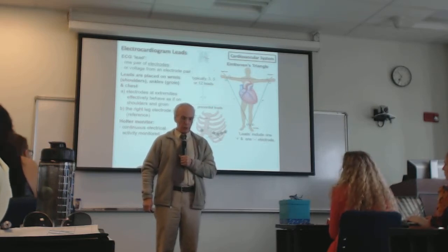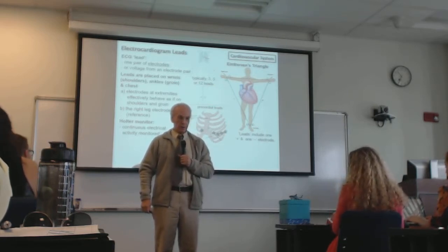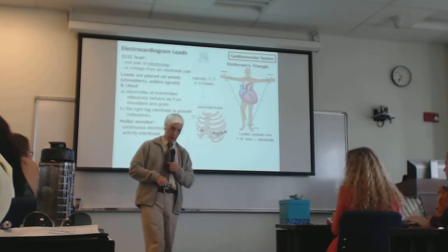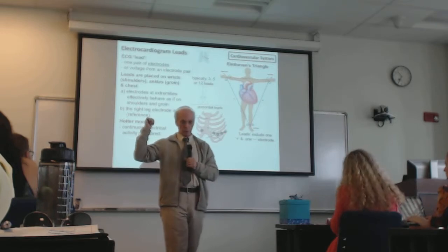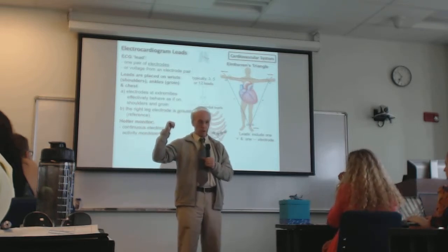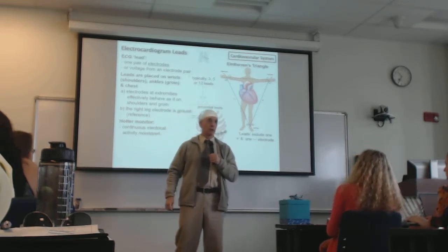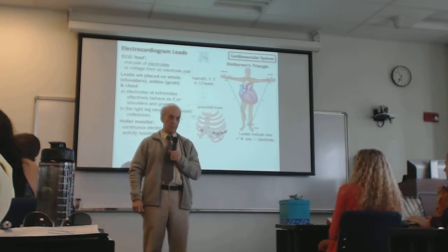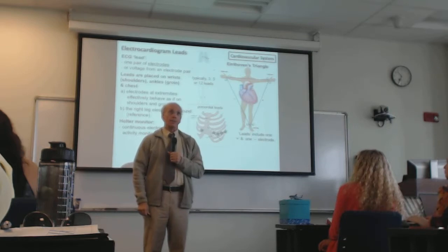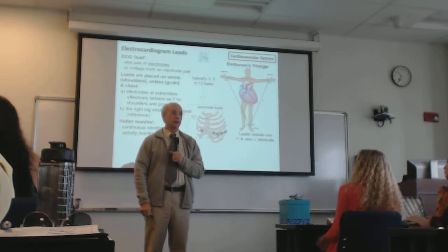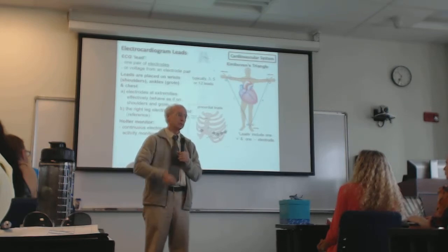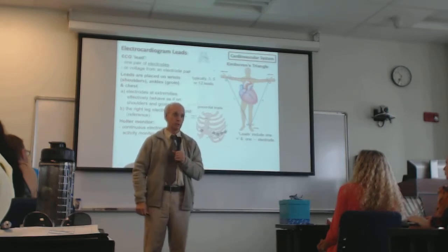My question for you: let's say I set the EKG up, and in my bipolar lead number 1, Einthoven's triangle, I get a measurement at the QRS of, I will just make up a silly number, 25 millivolts. That's not realistic, but let's just make it 25 millivolts. I did that today. I come back tomorrow and it's 18 millivolts. Put it on somebody, it must be wrong. So I put it on Abby and I make the same measurement and I get 4 millivolts.